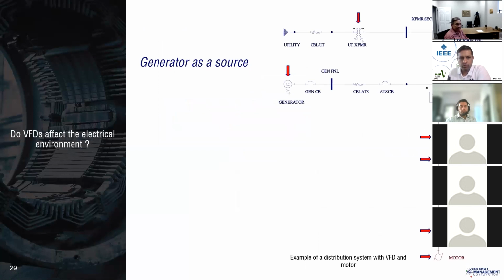Before getting into how installing an input reactor changes the total harmonic distortion of current, I just want to back up a little into the bigger picture, which is the electrical distribution system. I want to focus on generators, and have a discussion on how generators and VFDs go hand in hand. You should not be surprised that planning for harmonics is one of the aspects we consider while sizing generators. Sizing generators is one of the topics that gives a very good perspective of how a generator and a VFD go hand in hand.